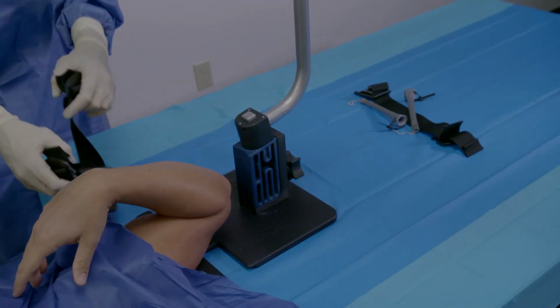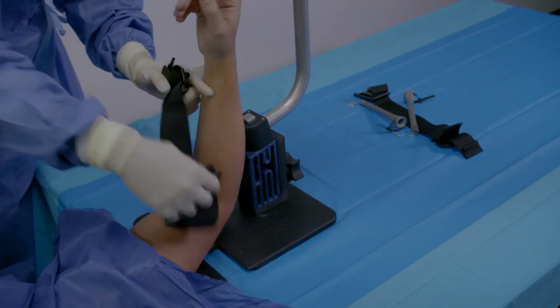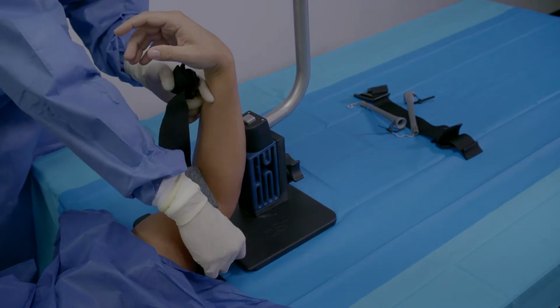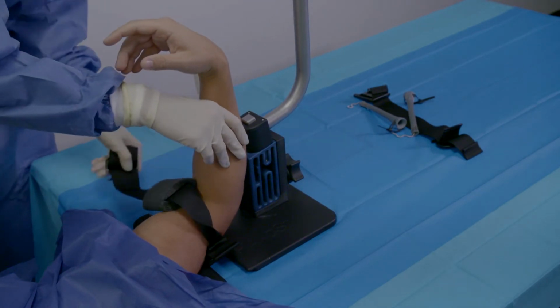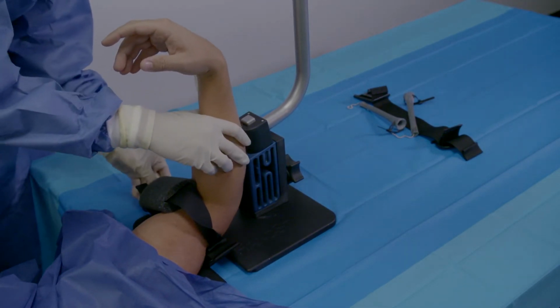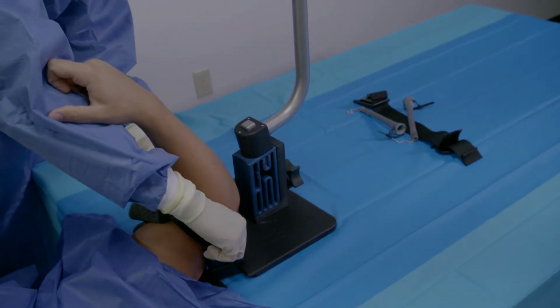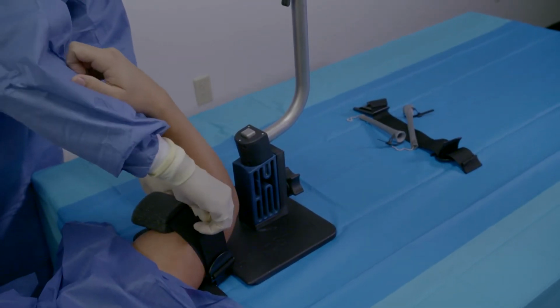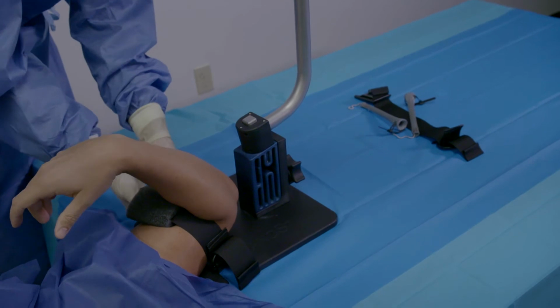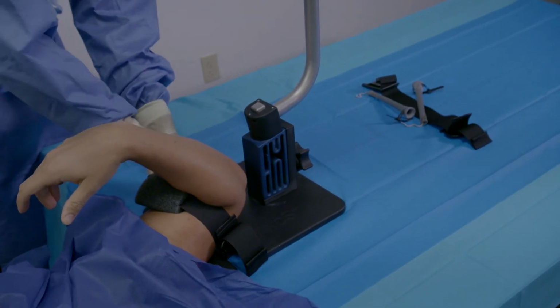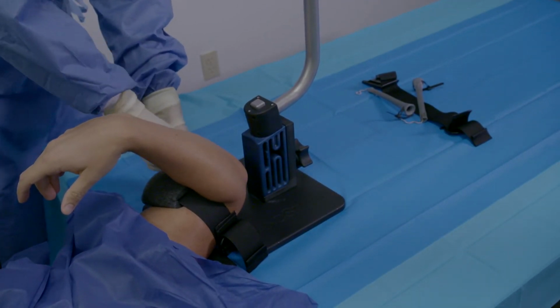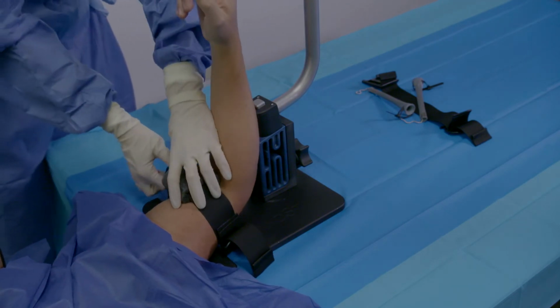To secure the patient's upper arm to the handstand tower, place the buckles of the bicep strap in the channels on the base plate until they're next to either side of the patient's arm. Adjust the strap length until the patient's arm is secured to the base plate. Then, ensure that the foam on the bicep strap is centered over the patient's arm.